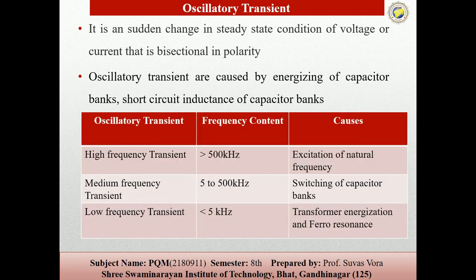High frequency transients have a frequency content greater than 500 kHz and are caused by excitation of natural frequencies. Medium frequency is between 5 to 500 kHz and is caused by switching of capacitor banks. Low frequency transients are less than 5 kHz and are caused by transformer energization and ferroresonance. These are the causes of high, medium, and low frequency oscillatory transients.